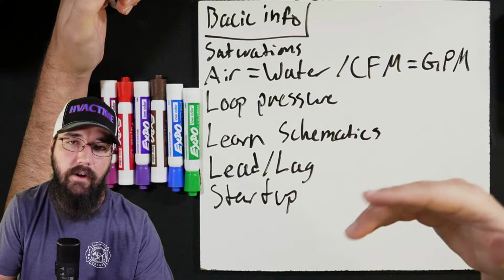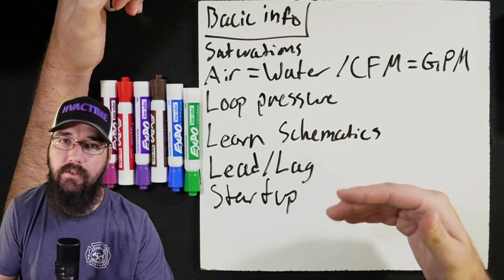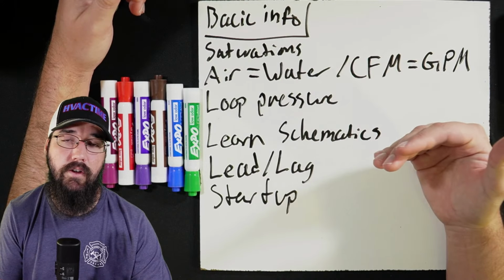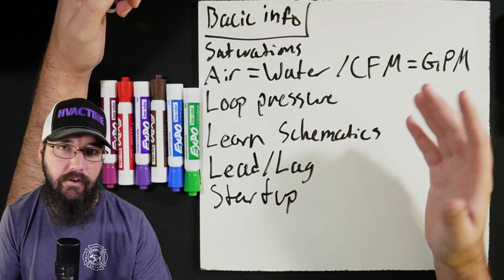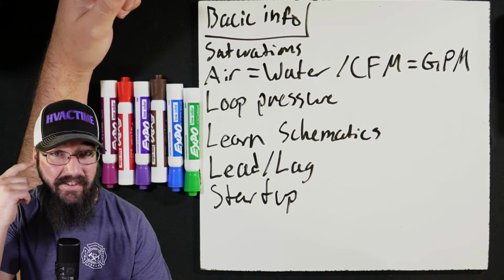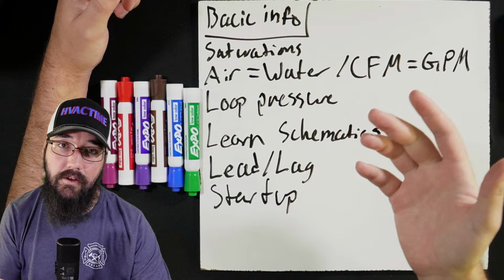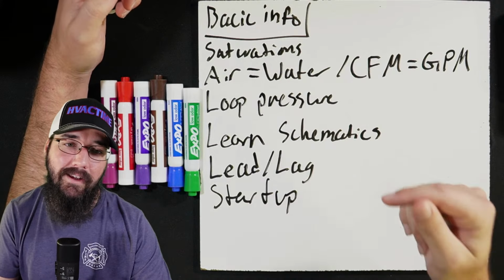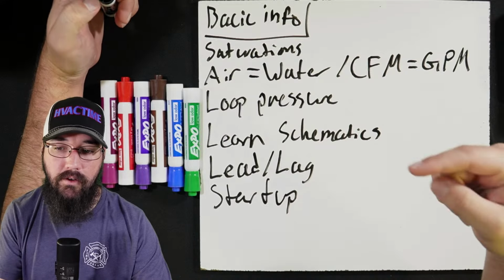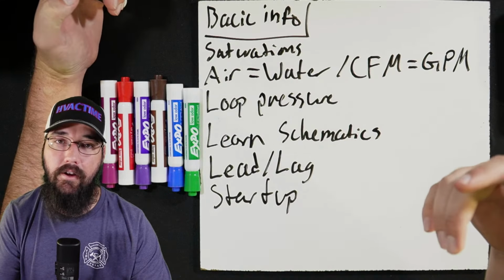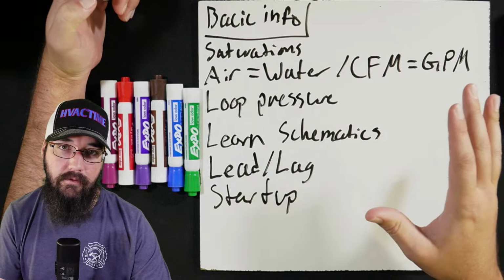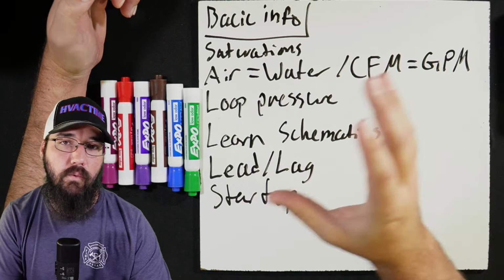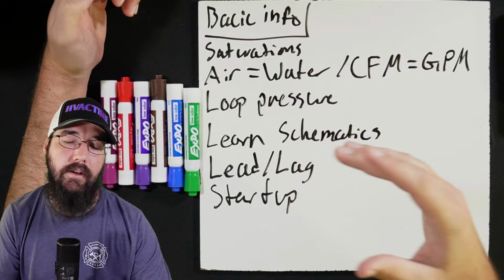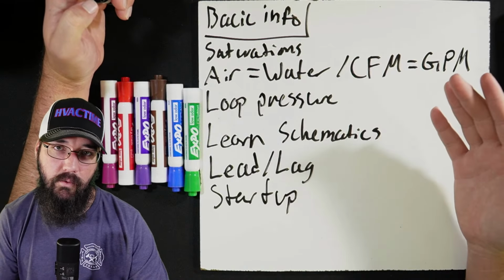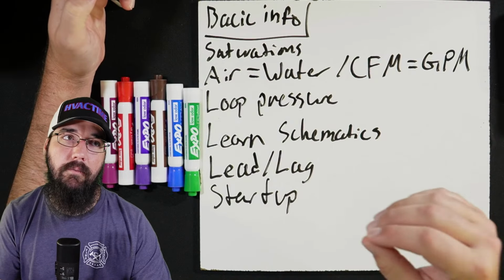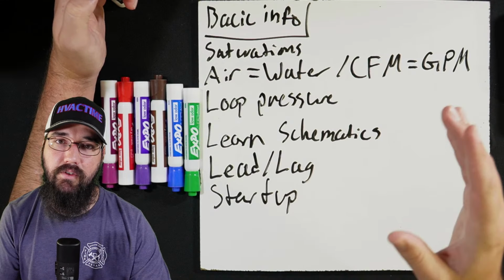And right, fan proving. So fan proving safety is also going to be the same thing as a flow switch. Those things are fully interchangeable in terms of concepts. They work different, one does air, one does water, but the concept of what is happening and why we need it is the same, because we won't start compressors until we prove fan on a commercial RTU. Period. If you're not working on that equipment, that may not be as helpful to you, but if you have at least gotten into some of that equipment, those are basic startup procedures that fully translate.